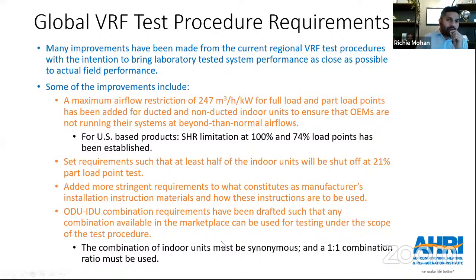And another massive or rather big change that we're adding in to the global standard is the combination requirements. So what sort of indoor units are you going to use in combination with the outdoor unit, such that that overall combination is more representative of what really gets installed in the field. If we're basically going ahead and testing a combination which will never be installed in the field, then the overall testing method and the rating method becomes much less effective.